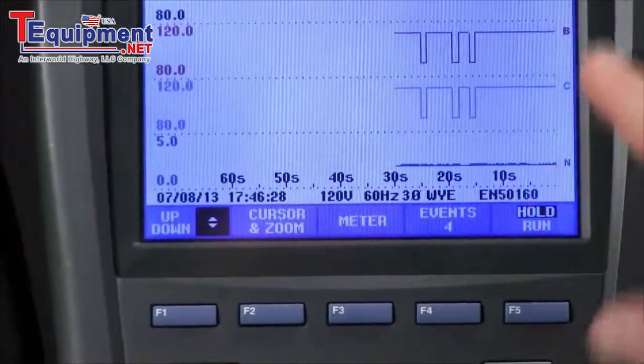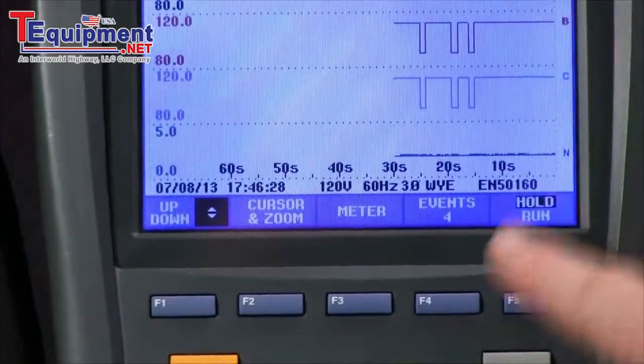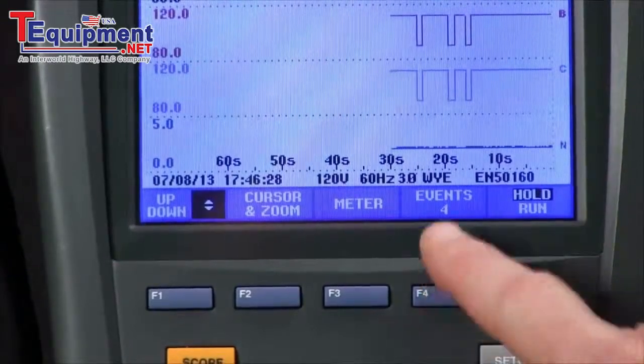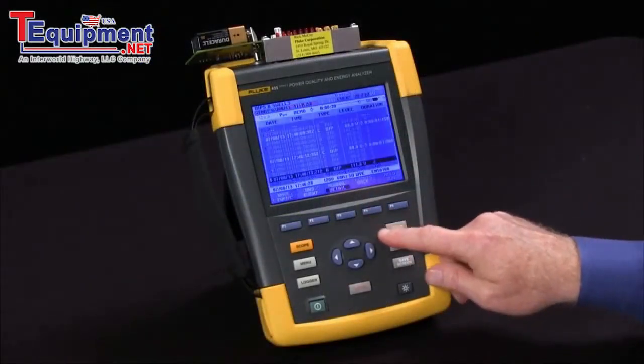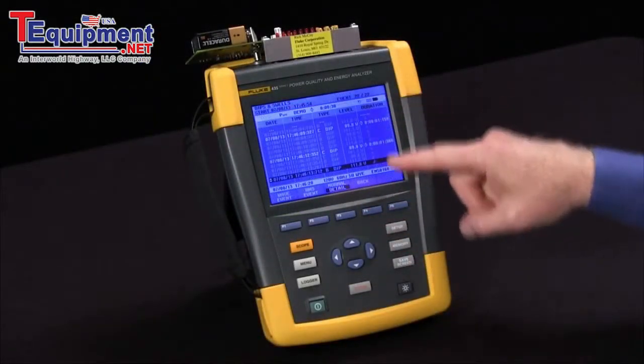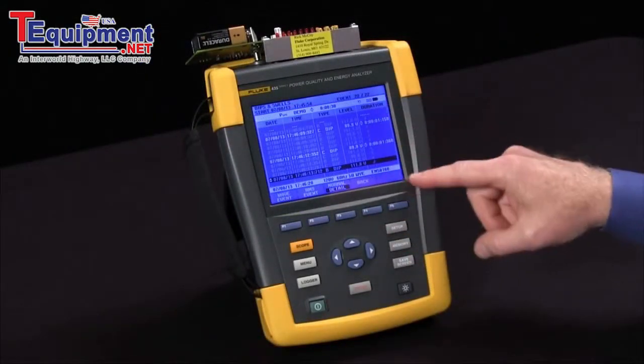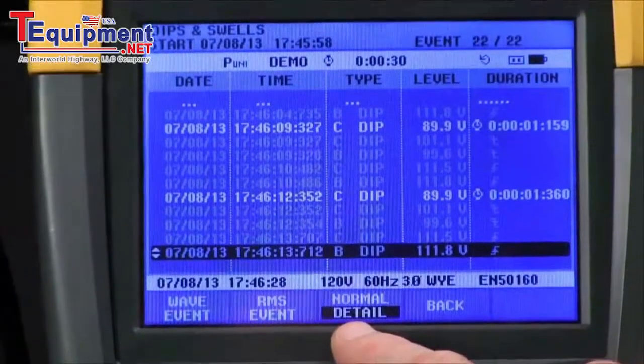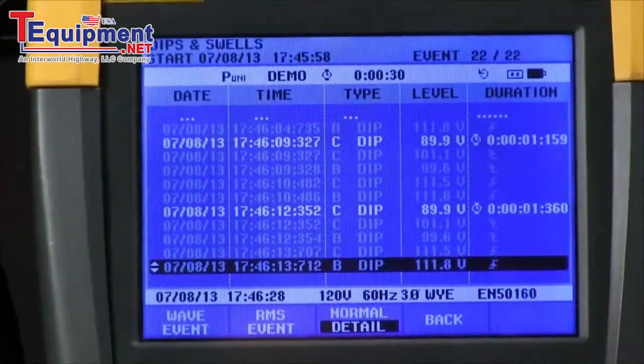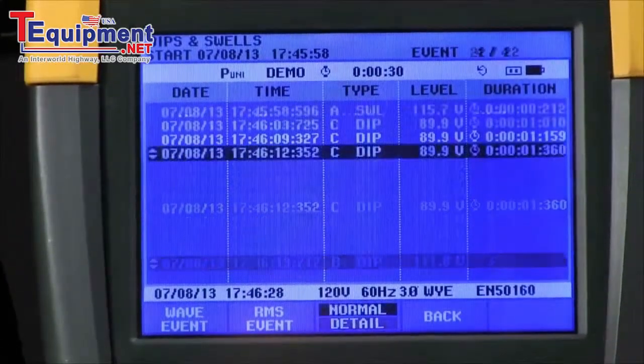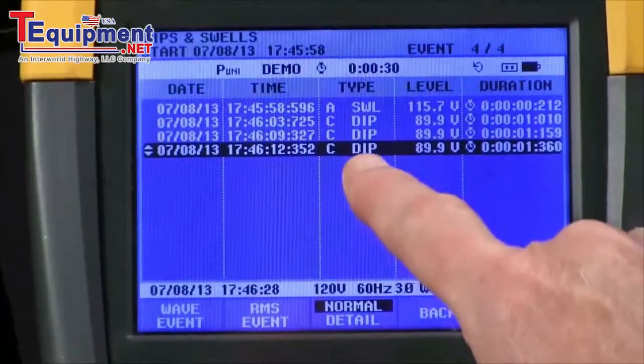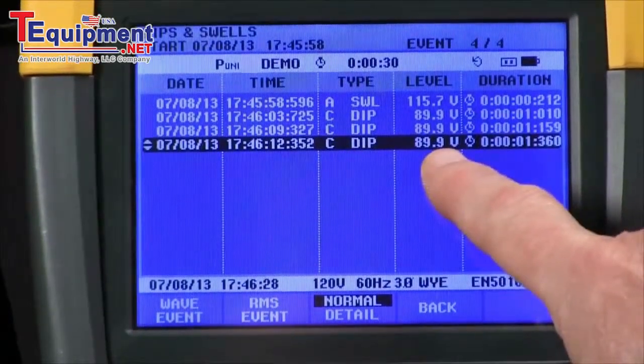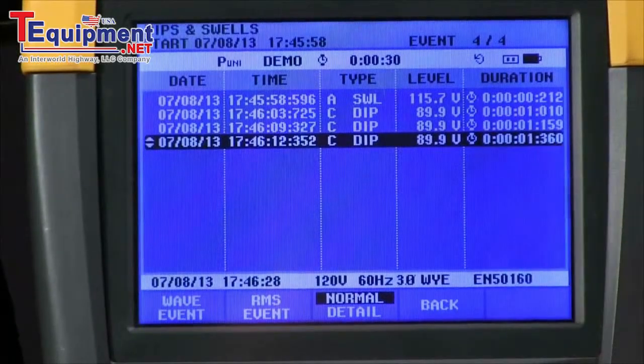We're back to our live screen. To analyze, we hit the F4 button to look at the events. Now we can see a listing of everything that was captured. This is the detailed screen right now — F3 gives us a normal display, and you'll see you've got a number of dips, the voltage level achieved, and the duration.